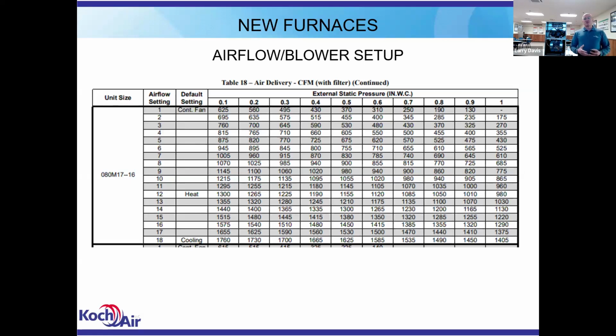Each furnace, based on its size, is going to give you a limited range that you can set your heating and cooling and constant fan speeds. They all come out of the box set at a default setting. The question early on was, do we have to go through and set these furnaces up before they'll run? And the answer is no. You can take a furnace out of the box, install it, land your thermostat wires, fire it up, and it'll run.